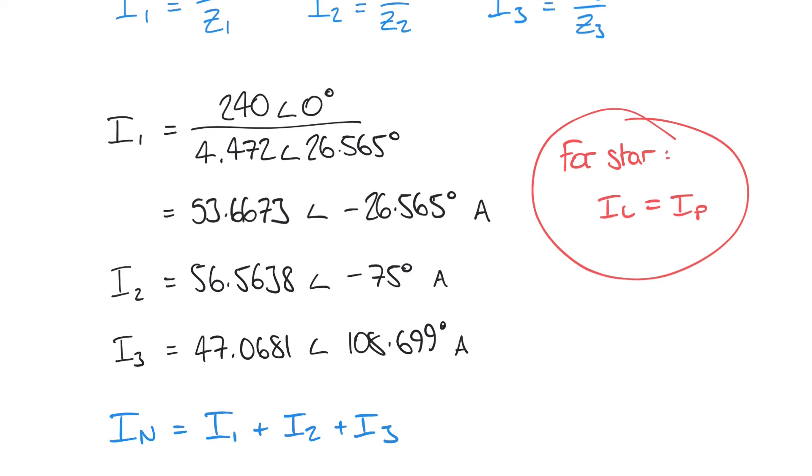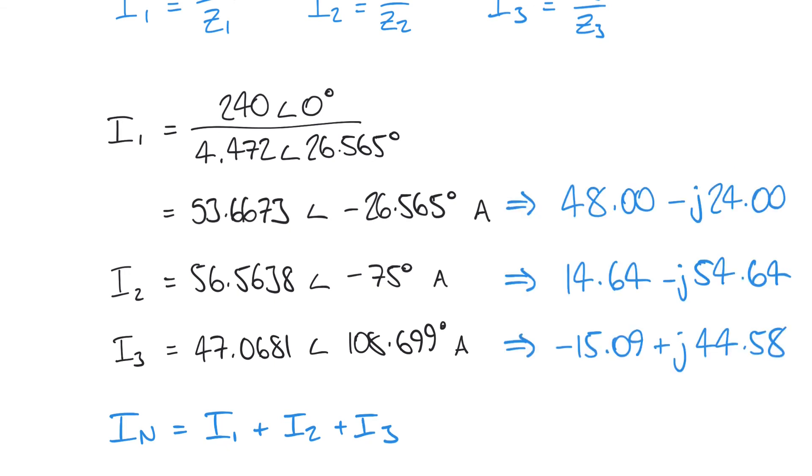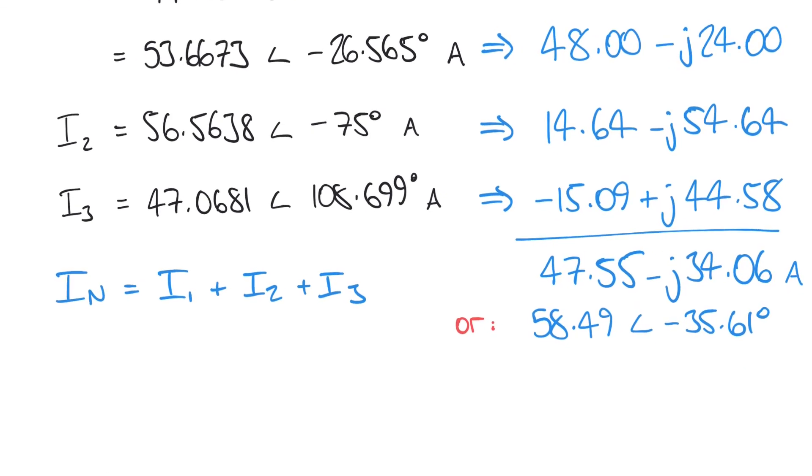What we'll do is convert these back just using the rec function on a scientific calculator to rectangular form. We have i1, i2 and i3 in rectangular form, and when we add those together we get a total neutral current that is not zero, as was the case in a balanced network. In this unbalanced network we're getting a non-zero neutral current of 47.55 minus j34.06. We can convert that back into polar form, which comes out as 58.49 at an angle of minus 35.61 degrees.